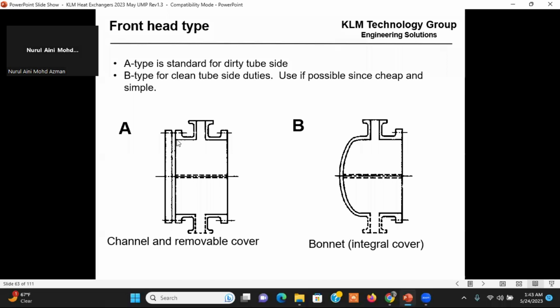A is for standard dirty tubes where you have to take this plate off and clean it. B is for a little more clean side duties. Use it if possible since it's cheap and simple. It's a little safer too. So in general, for hydrocarbons, I'm going to use a B. All right. For cooling water, I might use an A. For C, it's a removable shell for hazardous side materials, heavy bundles, or service. It means frequent shell cleanings. N is for fixed hazardous fluids on the shell type. D is for welded or tube sheet bonnets for high pressures over 150 bar. So they've got A, B, C, N, and D types for the front end. Okay, so these are the front half of the heat exchanger.